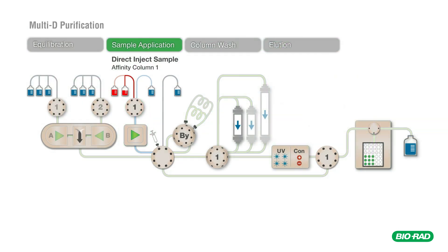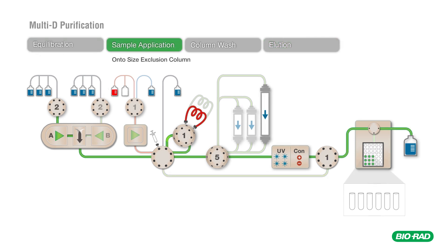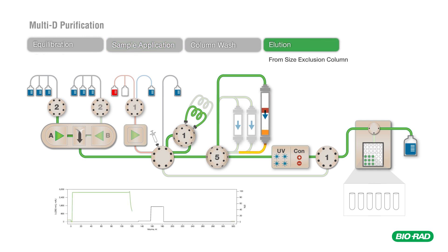In a typical Multi-D workflow, samples are loaded onto a column using an integrated sample pump. After flow-through and unbound material are washed away, the eluate is shuttled through the detector to identify proteins of interest. Those fractions are then sent directly to a static loop for storage. Once all of the protein of interest has been captured, it is then directly injected onto the second column and eluted to the fraction collector.